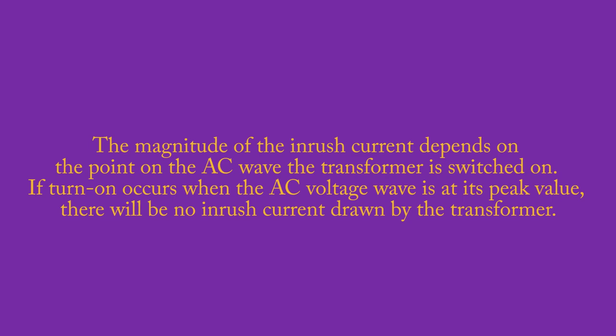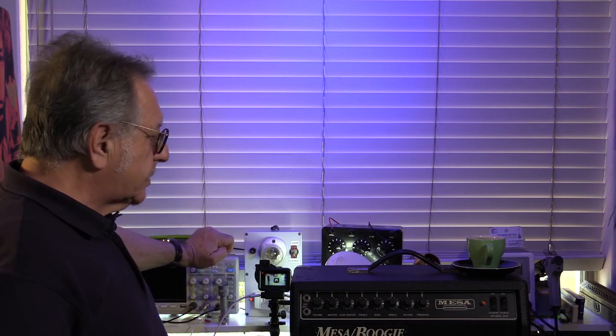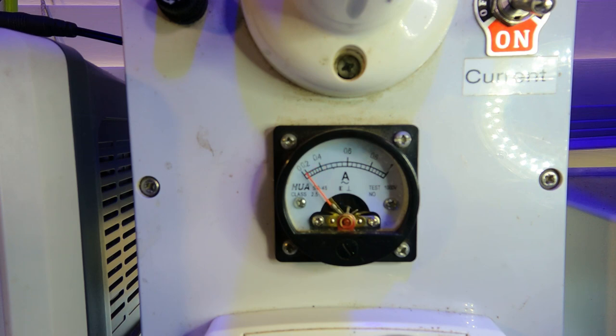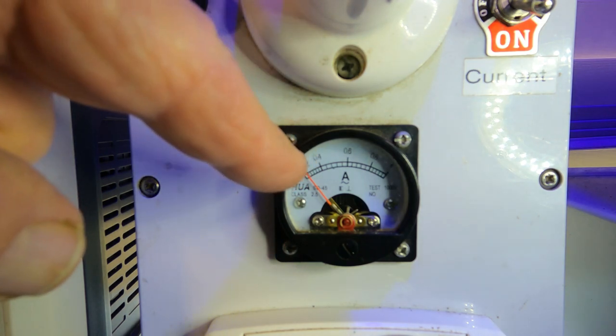Now if you keep your eye on the meter here, you will see two inrushes. The first will be when we go from power off to power on, and that will be the transformer energizing - the transformer inrush current. Then I'll go from standby to play, and that will be our filter capacitors charging. Okay, here we go, power on. Now you saw that little pulse in current - that was our transformer energizing, and then it settles back down to almost zero.